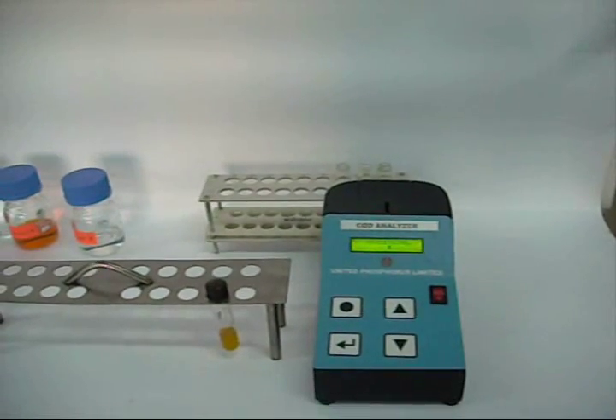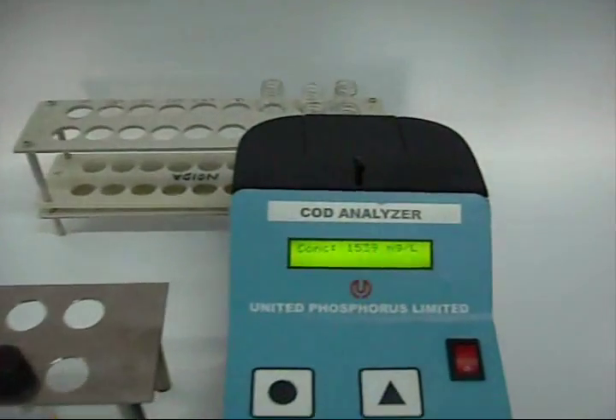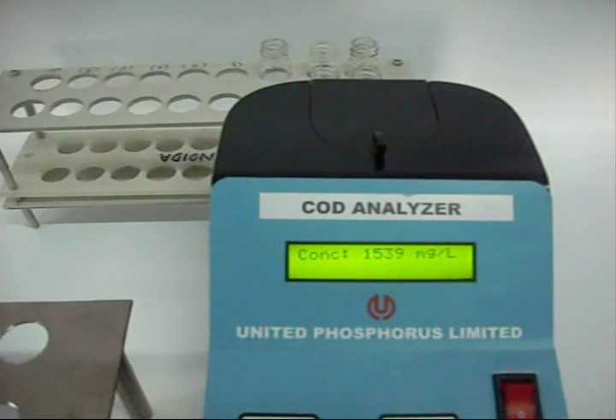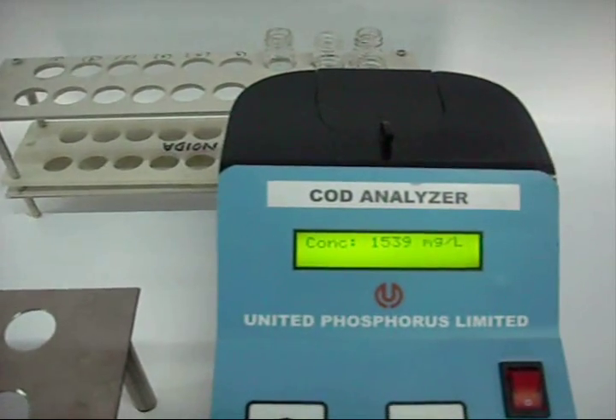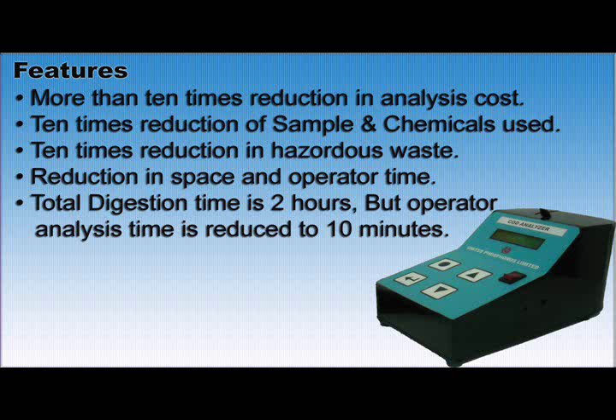Press the enter key if you want to log the data and save it on the microprocessor of the instrument. Features of the COD Analyzer include: more than 10 times reduction in analysis cost, 10 times reduction of sample and chemical use, 10 times reduction in hazardous waste, reduction in space and operator's time. Total digestion time is 2 hours, but operator's analysis time is reduced to just 10 minutes.